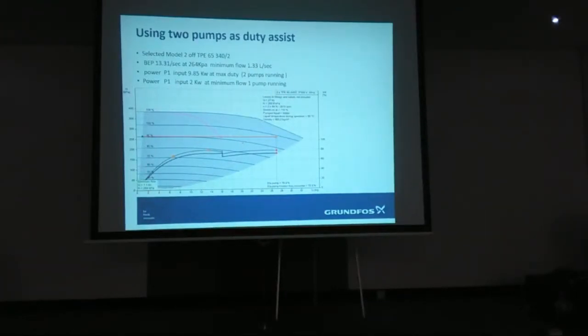So, is there an opportunity there of doing 1/3, 2/3? No. Because what will happen is, the one Nigel alluded to has got a jockey on it. Ideally, you could have 2 jockeys, so you're sharing the load, because one jockey will run throughout the summer until people wake up in the morning. It's like a cold water booster system. Not many people use jockeys nowadays, because variable speed pumps cover quite a wide range. So multiple pumps isn't necessarily more expensive than duty standby. We go to a maximum of 6, for example, duty, assist, standby, whatever. I always make sure the last one can run as well.